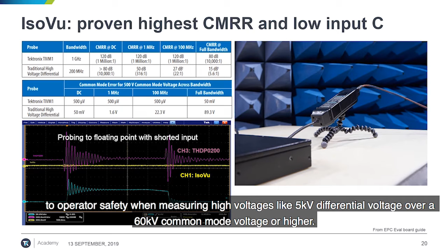The probe itself is designed to add the minimum load burden to the circuit, as we will see in the next slide, and also to optimize connectivity to your circuit with a long list of special new types of leads. Do not underestimate that a purely optical probe with up to 10 meters fiber length is essential to operator safety, especially when measuring high voltages like 5 kV differential voltage over 60 kilovolts of common mode voltage, or higher.